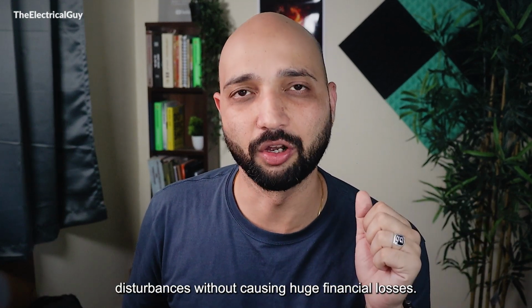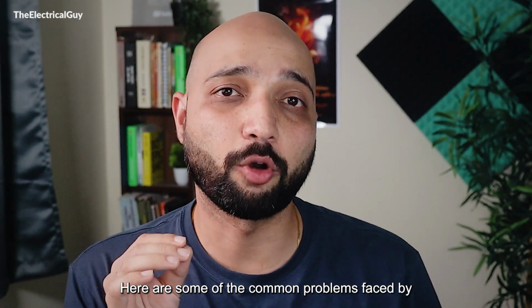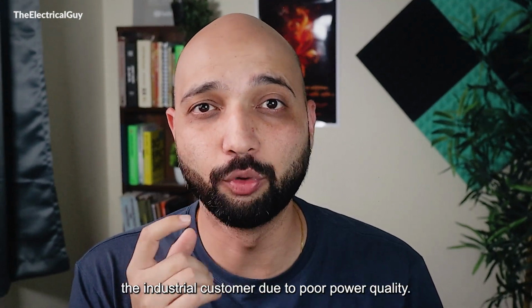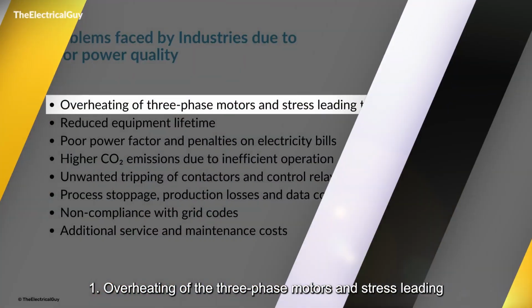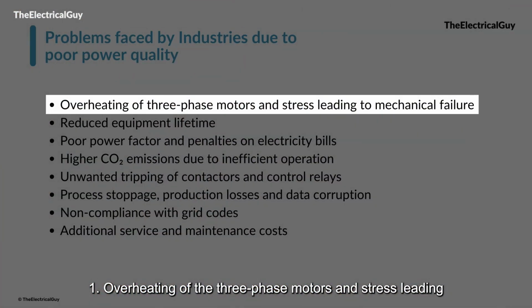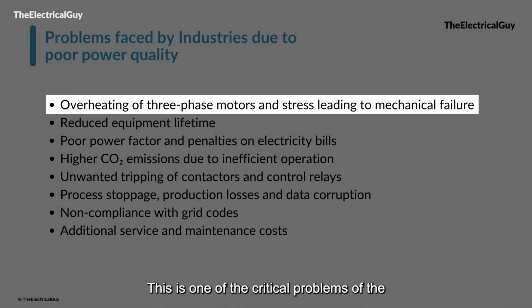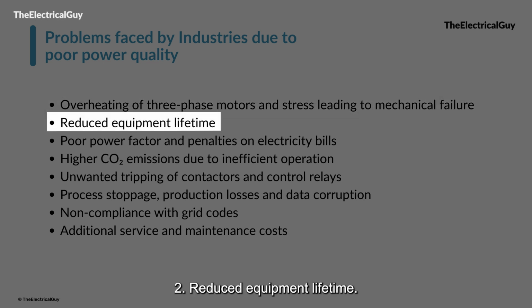Here are some of the common problems faced by industrial customers due to poor power quality. First, overheating of three-phase motors and stress leading to mechanical failure. This is one of the critical problems of the industry, where the motor fails to start or just overheats. Then reduced equipment lifetime, again because of the heating, the overall life of the equipment will go down.